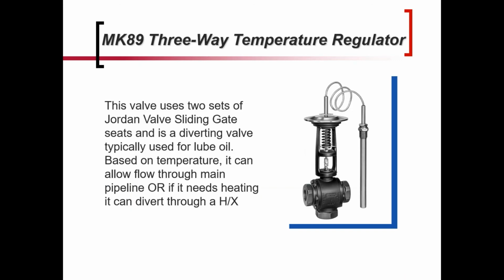And there are three-way versions. These are usually hot oil applications where you're heating it, and if the oil drops below a certain temperature, it can divert the oil through a heat exchanger to heat it back up. So see that pretty often. And when I do see a three-way type temperature regulator specified for something, it's typically a hot oil application.